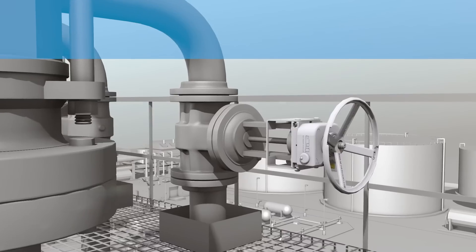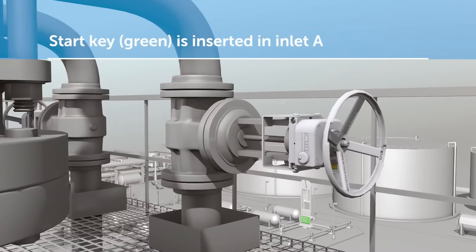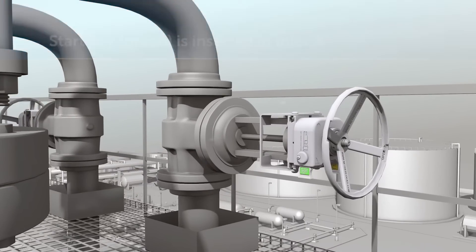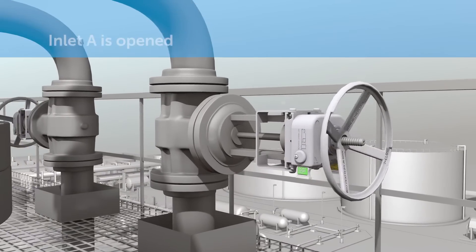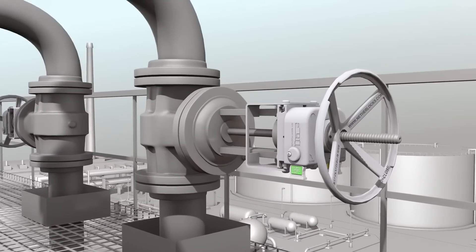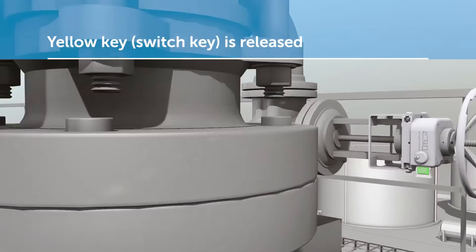The start key unlocks inlet valve A. Another key is trapped inside. Once inlet valve A is opened, the start key is trapped and the second key released.